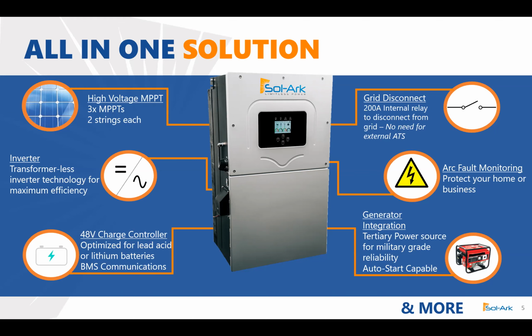We also have arc fault monitoring and ground fault monitoring to protect your PV and make sure there are no ground faults in the system. And we can integrate with any generator. It's a great tertiary power source. You can connect to any 240 volt or 208 generator, and we can automatically start that generator via a 2-wire start based off the battery's programmed state of charge. It really helps you utilize the generator only when needed, so you're not running it constantly.